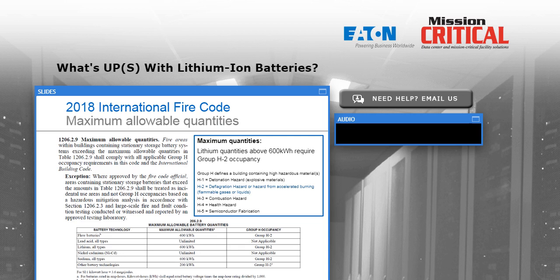Each of the battery cabinets that we saw on the previous slides are about 33 kilowatt hours. So I would need to have a lot of lithium battery cabinets in the same room in order to move up to group H2 occupancy, which is the one that has the more stringent fire suppression and fire reduction requirements. This information will be publicly available in July.